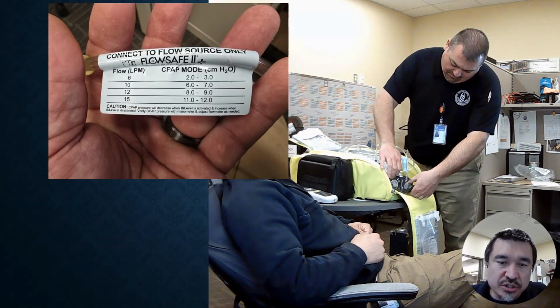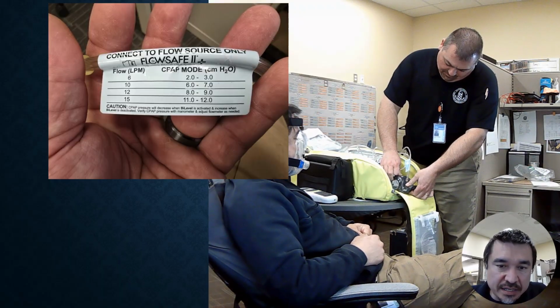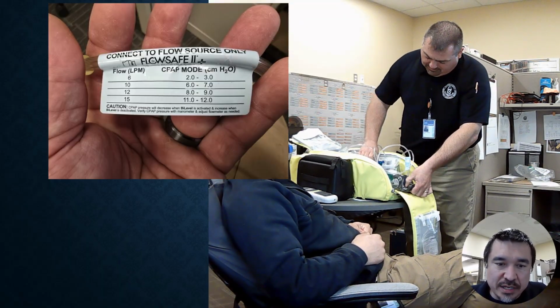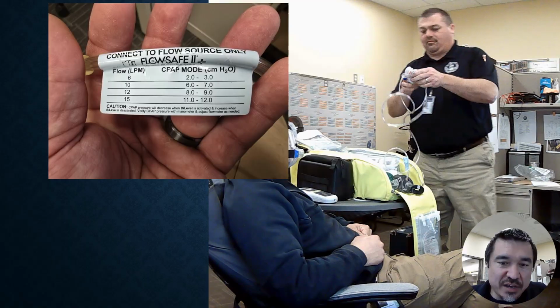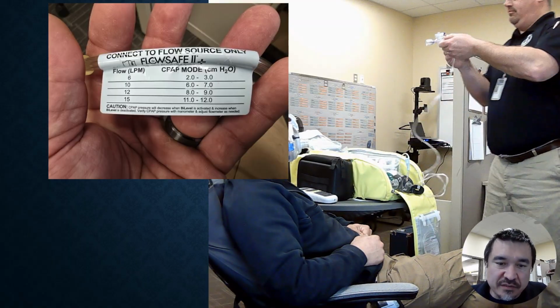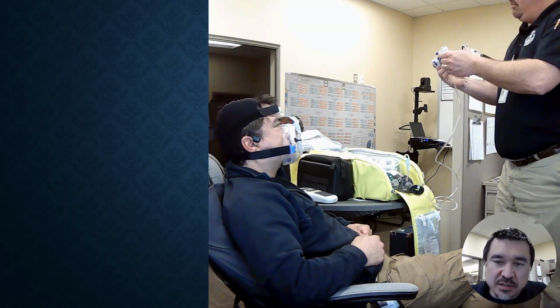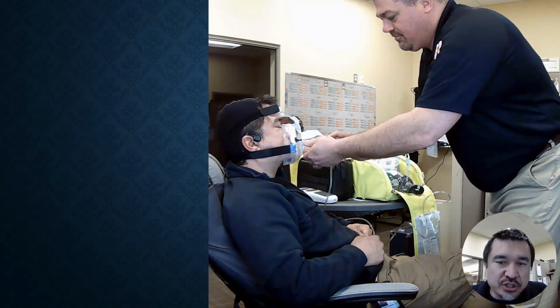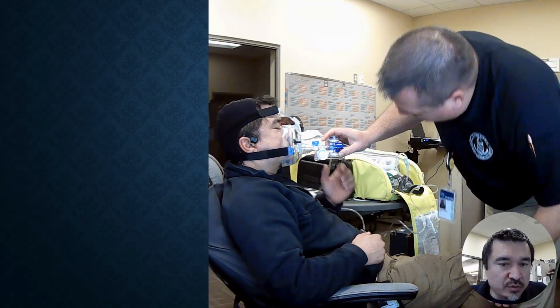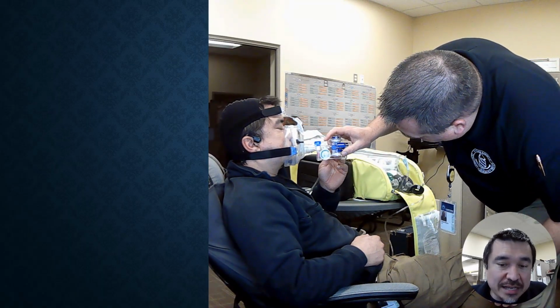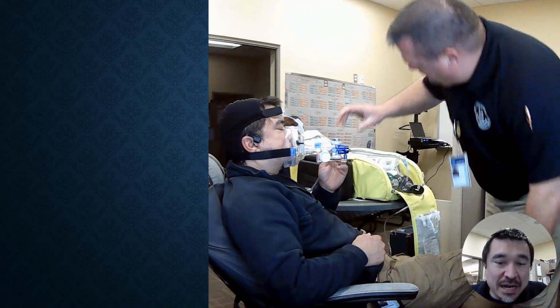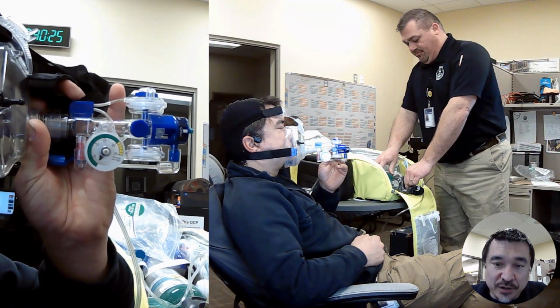Now on the oxygen tubing, you're going to notice the oxygen flow setting. Set the O2 bottle liter per minute to correspond with the desired PEEP value. There's no spring device to set the PEEP. Using the manometer, you verify that you've achieved the desired PEEP, and then you would just adjust the oxygen flow regulator as needed.